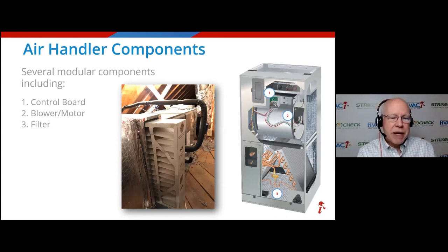And in this picture, which I didn't mention earlier, I talked about an upflow furnace. Well, here's an air handler that's laying on its side. That would be a horizontal unit, normally in crawl spaces and attics. Most units, when they come off the manufacturing floor, are designed to be installed either direction, so don't get too caught up in that. Notice that filter is before the unit. All right, the return ductwork is coming in, goes through the filter, then through the air handler. All right, it's critical that we do that.